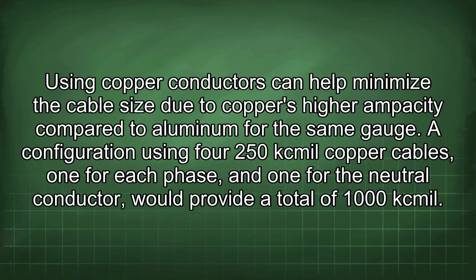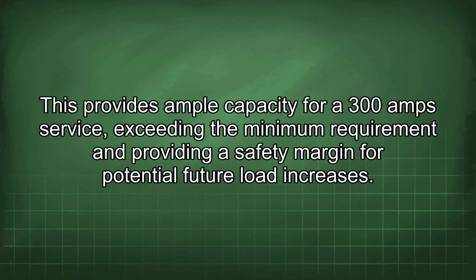Using copper conductors can help minimize the cable size due to copper's higher ampacity compared to aluminum for the same gauge. A configuration using four 250 kcmil copper cables, one for each phase, and one for the neutral conductor, would provide a total of 1000 kcmil.